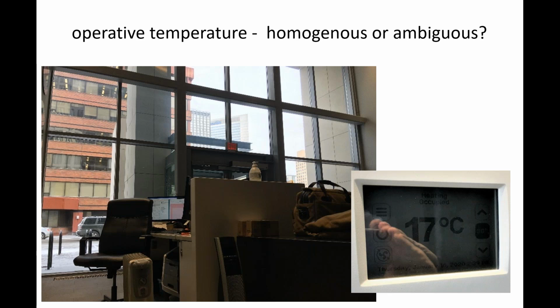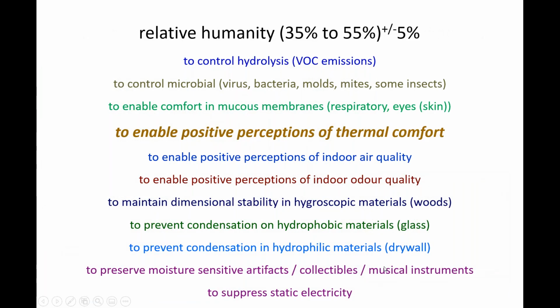You can blow all the hot air into a room like this all day long, that glass temperature, even if it's a high performance glass, triple pane, triple sealed, argon filled, doesn't matter. The glass inside surface temperature at minus 40 degrees Celsius will be approaching somewhere around 8 degrees C, 10 degrees C, something like that. It's incredibly cold. So that's important.